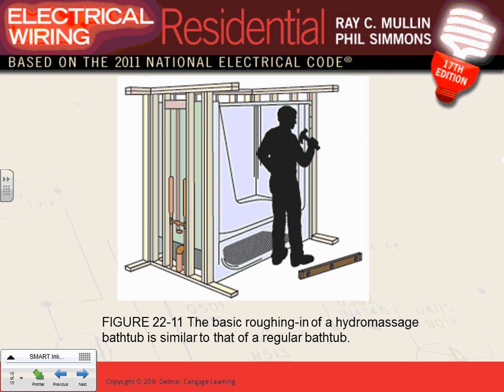One last thing, guys, for hydromassage bathtub that you have to understand. If you have a motor, here's my motor here, you have to bond the mechanical equipment to the motor frame with number 8, I believe. Number 8. Can I have your attention, guys? When you have a hydromassage bathtub, one very, very interesting situation that you don't do elsewhere. That's when they test you guys on your master tool. Here's the motor sitting here, the frame of a motor. You're supposed to bring a number 8 copper insulated or bare conductor, and you tie it to the pipe system from one side and to the frame of the motor from the other side. They call it bonding conductor. You bond the mechanical equipment to the electrical equipment. That's required for hydromassage bathtub.